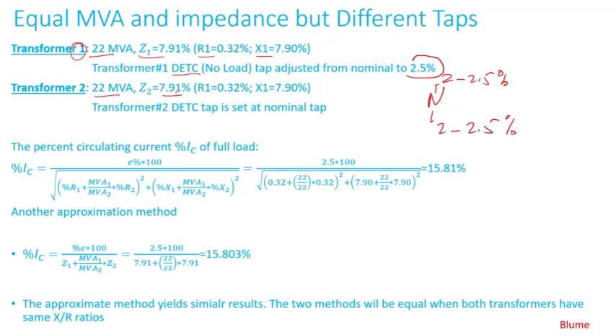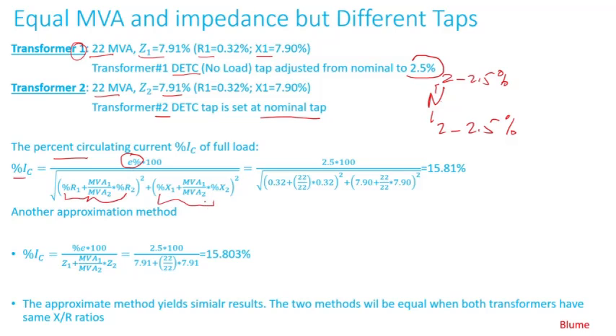Transformer 2 has the same MVA and same impedance, but is set at nominal tap. So the turns ratios do not match. There is a formula for calculating the percent circulating current — the difference in voltage between the two transformers times 100%, divided by the square root of the combined impedances, with resistances and reactances placed on the same base.